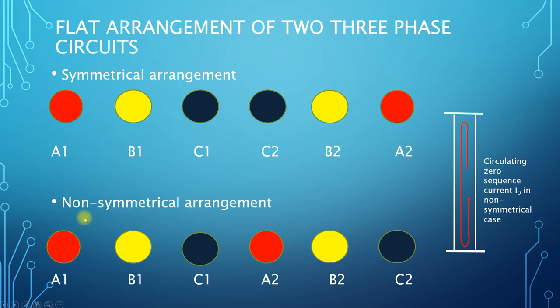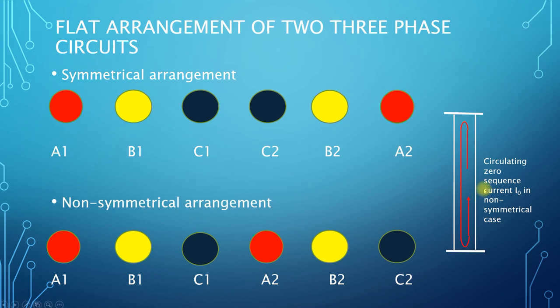An example of a non-symmetrical arrangement would be to simply lay the conductors in phase order. So in this example, we have A1, B1, C1 of circuit 1 followed by A2, B2, and C2 of circuit 2. With this arrangement, there will be a strong circulating current between the two parallel three-phase circuits.